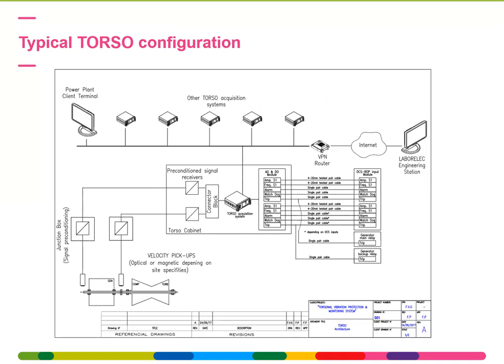Here you can see an overview of the typical torso configuration. So how does a torsional vibration monitoring protection system look? Well, it begins, of course, at the machine. So here it's a gas turbine. You can have 1, 2, 3 sensors. For a protection system, you need at least 2 to have the required redundancy.